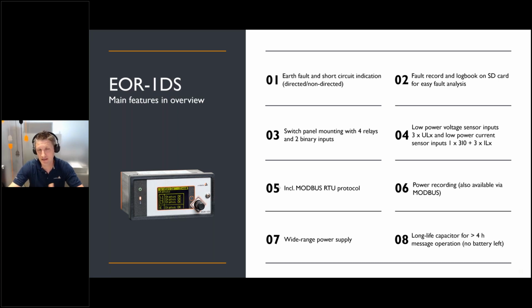It is a device for switch panel mounting, has 4 relays, 2 binary inputs, and is capable not only of current measurements via these 3 orange Rogowski coils. It can also measure the voltage in parallel via a VDS system. So you might know a CAPDIS or WEGA device, for example, a voltage detection system, and can measure the voltage in parallel. But not only these 2 options are possible to measure current and voltage in a not so accurate manner. The device is also capable of using low power voltage and current sensors with measurement class 0.5. And then it also makes sense to measure the power values, for example.